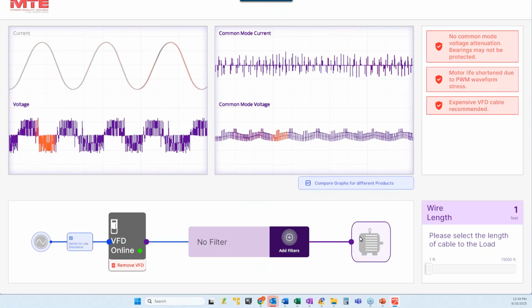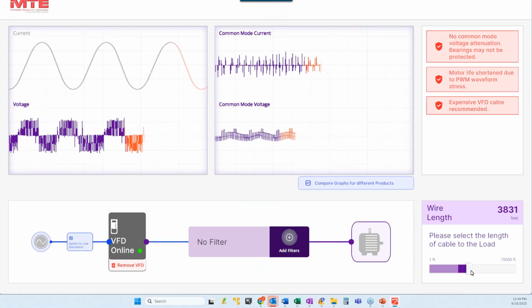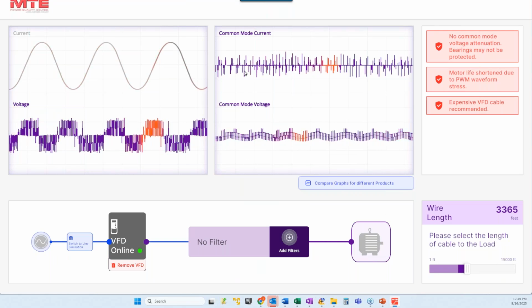But what happens is, depending on the length of the cable, we'll just go 33, you got what they call common mode voltage and common mode current. What happens is the longer the cable is, then I've got capacitance between those cables, and you're actually creating voltage spikes. So you need to go in there and clean those up and clean up those current spikes. Remember when we first started selling motors with drives, we'd burn up the motors because the motors were seeing like 2,000 volts and the insulation on the motors wasn't designed properly. Now all the VFD motors have higher insulation ratings just to handle that.